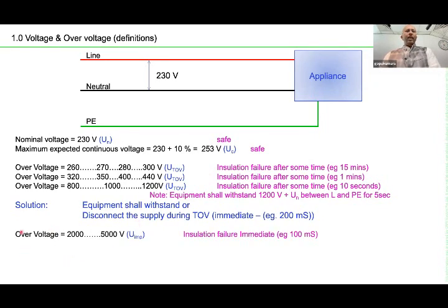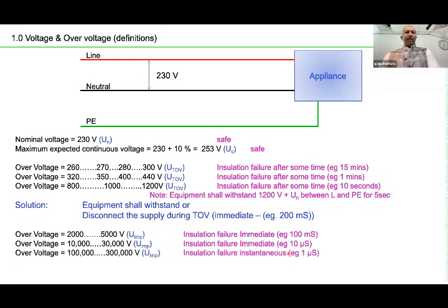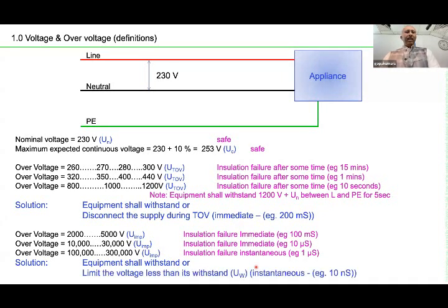Similarly, if the voltage is not 1 kV or 2 kV, but 5 kV or even very high voltage, insulation failure will happen very quickly, maybe in 100 milliseconds. With an even higher voltage, the failure will be much faster. So under these conditions there are two solutions. Either the equipment withstands, which is impossible, as you know very well, or we limit this transient over voltage.